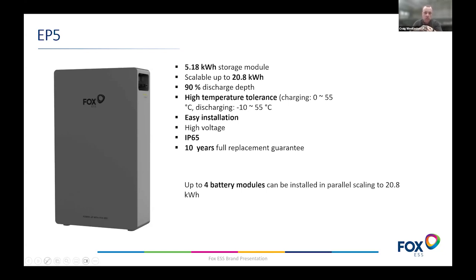The EP5 is a 5.18 kilowatt hour module. These go in parallel when you scale rather than series, the Energy Cube you install in series, as mentioned, circa 50 volts each. These are high voltage batteries, 190 volts plus, and then you parallel when you want to scale. Now when you parallel these, you do need a junction box to parallel them.